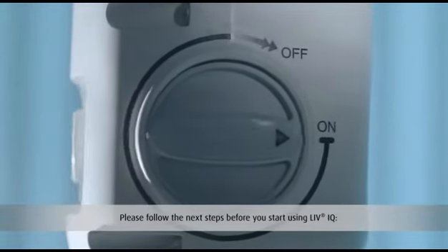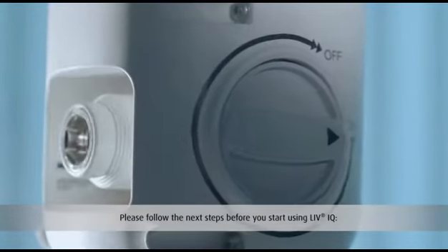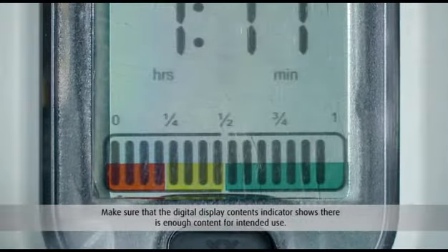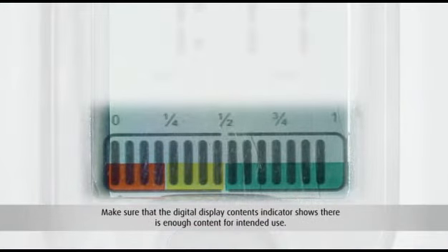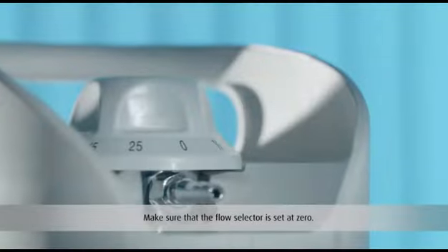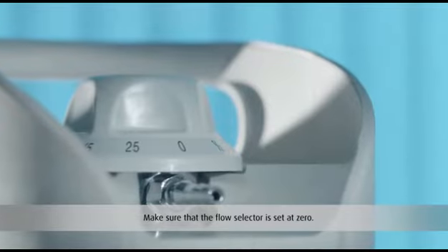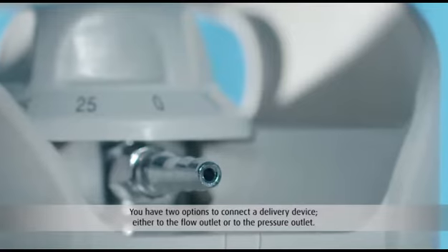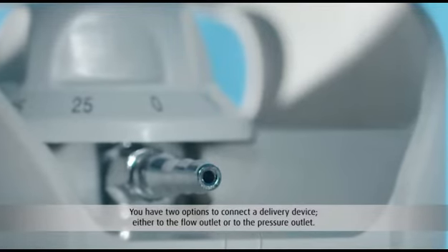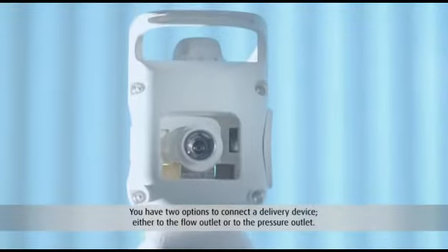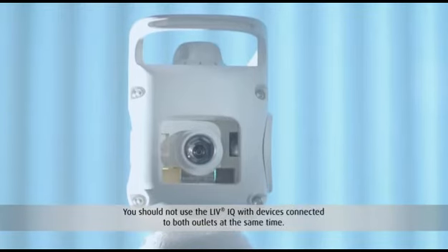Please follow the next steps before you start using LIV IQ. Make sure that the digital display contents indicator shows there is enough content for intended use. Make sure that the flow selector is set at 0. You have two options to connect a delivery device, either to the flow outlet or to the pressure outlet. You should not use the LIV IQ with devices connected to both outlets at the same time.